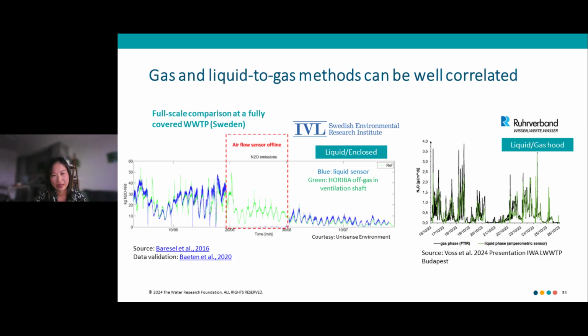There are some validation works trying to compare the accuracies between different methods. So this slide is showing some examples trying to validate between the gas phase measurement and the liquid phase measurement. The example to the left is a long-term validation at a full-scale wastewater treatment plant with an enclosed plant, so they can measure based on the liquid measurement calculation and the gas phase measurement from the enclosed plant. And the example to the right is a more recent work out of Germany. They are comparing the liquid sensor versus the gas hood, and still show pretty good correlation between the two methods.